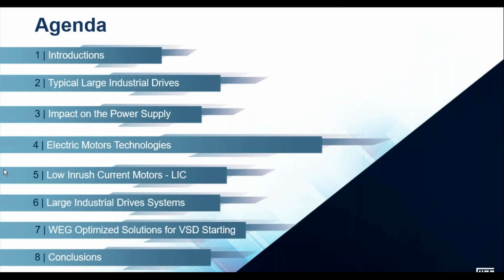Then in section 4, we look at the different motor technologies available in terms of construction design. And there we look at some typical motors in both induction and synchronous machines, and we just do a very high-level comparison of the different types. Then in section 5, we're going to narrow down to a specific motor design for low inrush currents, direct online starting. It'll become clear later, but that's an alternative to using a standard direct online motor with an indirect starting device. That's how we design a machine to reduce its starting current, which can be used in certain applications.